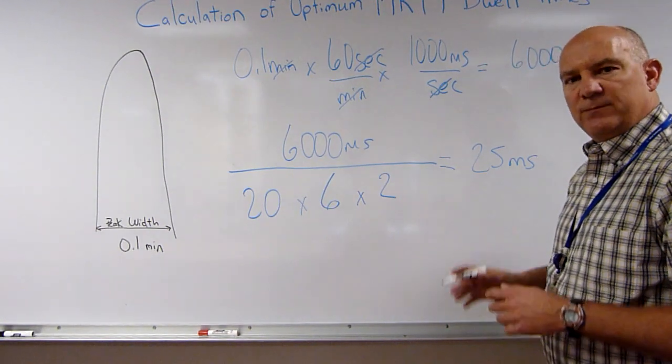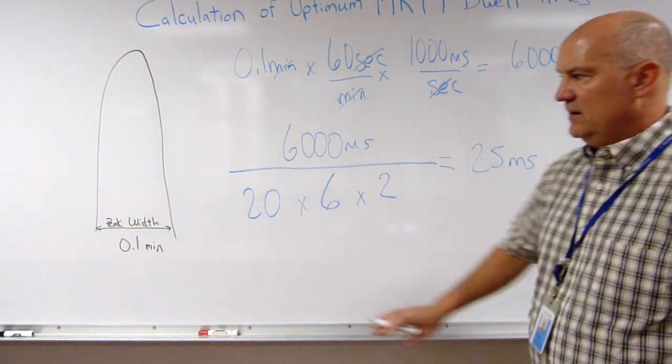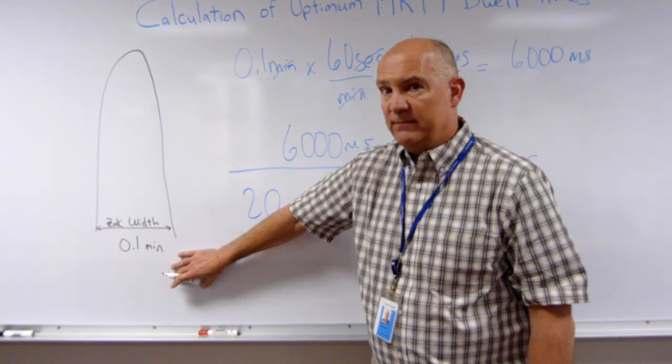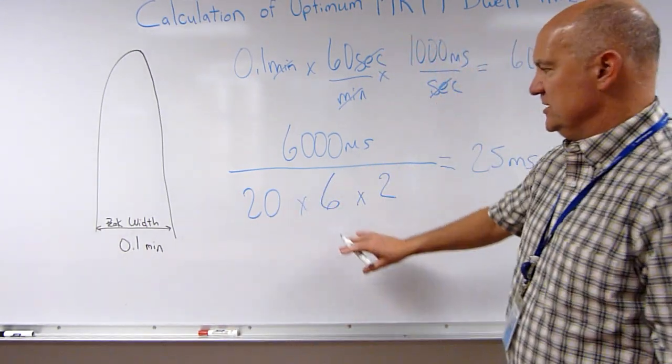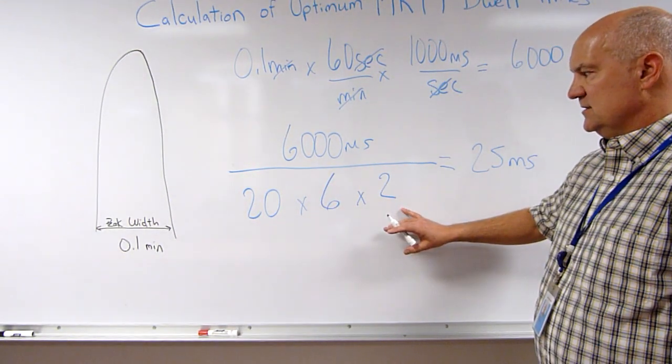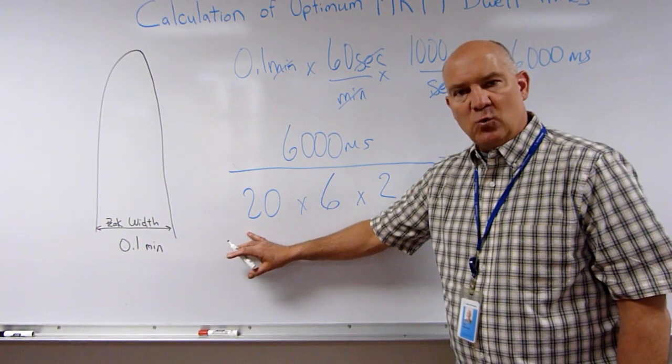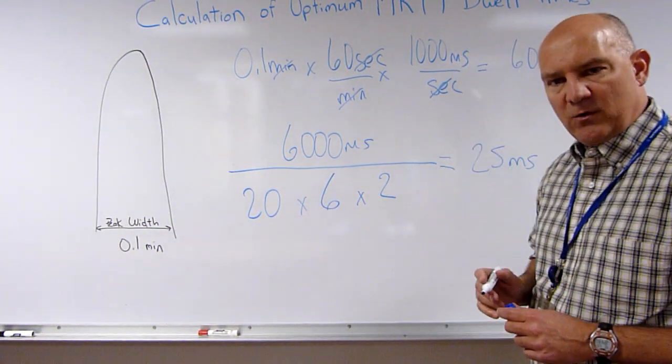25 milliseconds would be the optimum dwell time for this 0.1 minute peak if we were measuring 6 compounds and 2 transitions of each and desired 20 data points for every MRM transition.